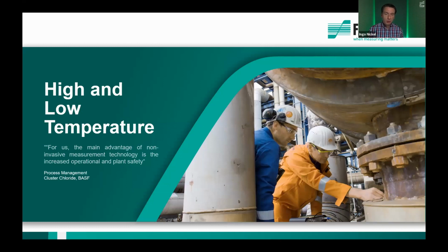Another challenge is temperature. We can have cryogenic temperatures within chemical plants for cooling applications. This means temperatures below -150 degrees Celsius, but also high temperatures up to 600 degrees Celsius are very challenging conditions for inline flow instrumentation. We also have a solution for this range of temperature, and we have special mounting systems which are able to provide clamp-on flow measurement under these demanding conditions. All of our sensors can be equipped with a patented thermal decoupling element to achieve a very reliable flow measurement also for extreme temperature conditions.